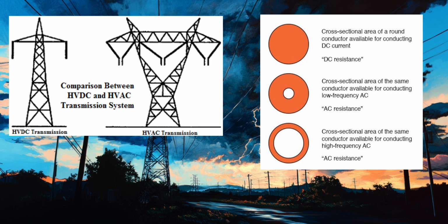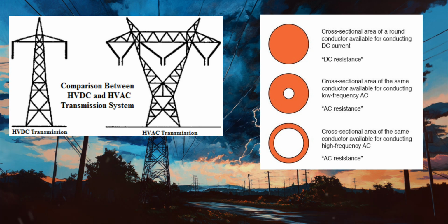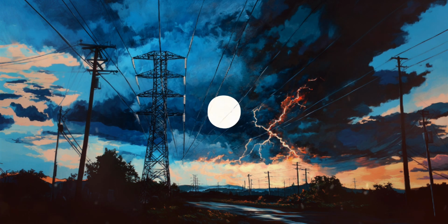The skin effect is an electrical phenomenon that occurs when AC flows along the surface of a conductor rather than throughout its entire cross-sectional area. This issue is not present in DC, so the same voltage transmission will require larger gauge conductors in AC than the equivalent DC. And the final point about cost efficiency is simple. DC only requires two conductors. AC requires three conductors and a neutral. This reduces the materials needed for the cables by one-third at a minimum.